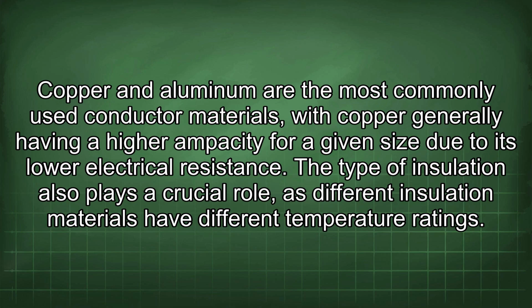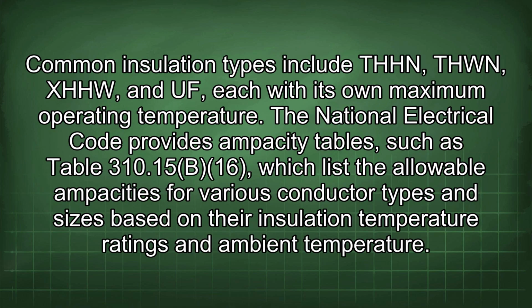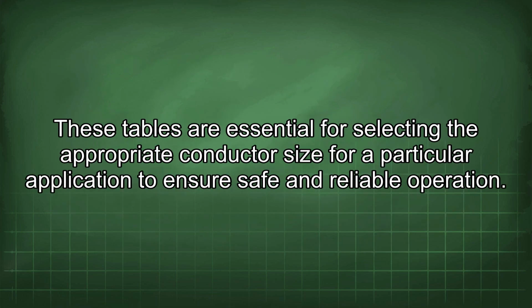The type of insulation also plays a crucial role, as different insulation materials have different temperature ratings. Common insulation types include THHN, THWN, XHHW, and UF, each with its own maximum operating temperature. The National Electrical Code provides ampacity tables, such as Table 310.15(B)(16), which list the allowable ampacities for various conductor types and sizes based on their insulation temperature ratings and ambient temperature. These tables are essential for selecting the appropriate conductor size for a particular application to ensure safe and reliable operation.